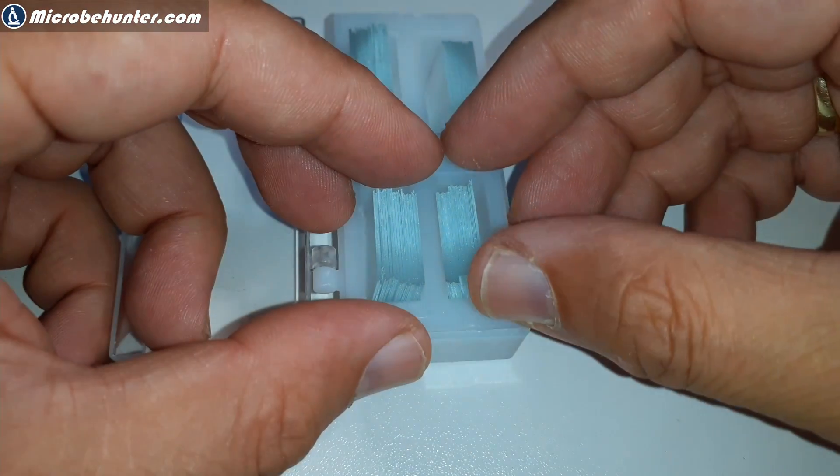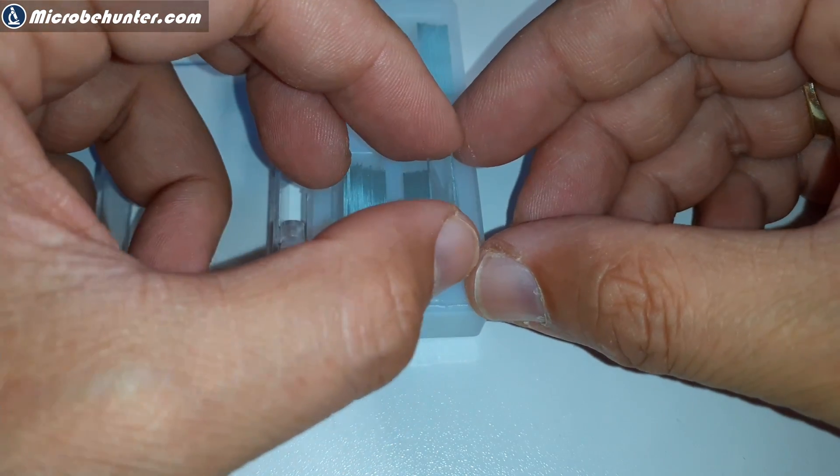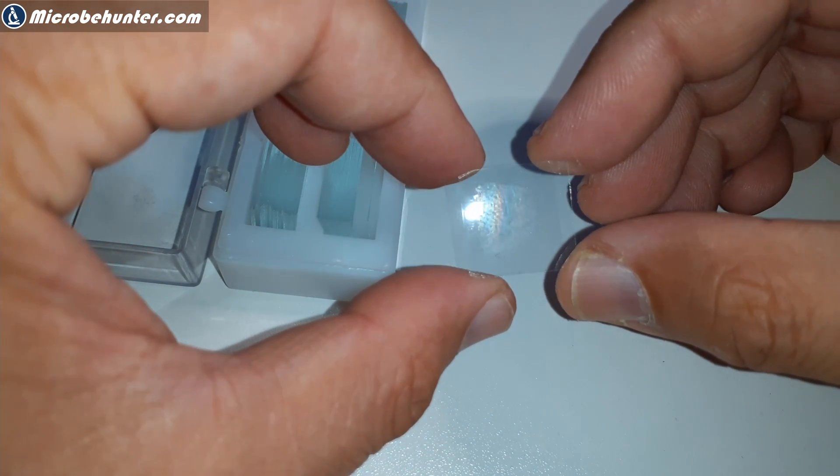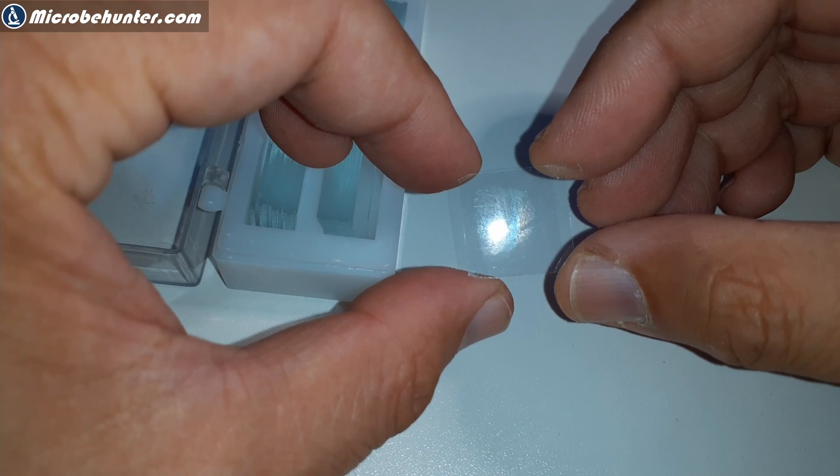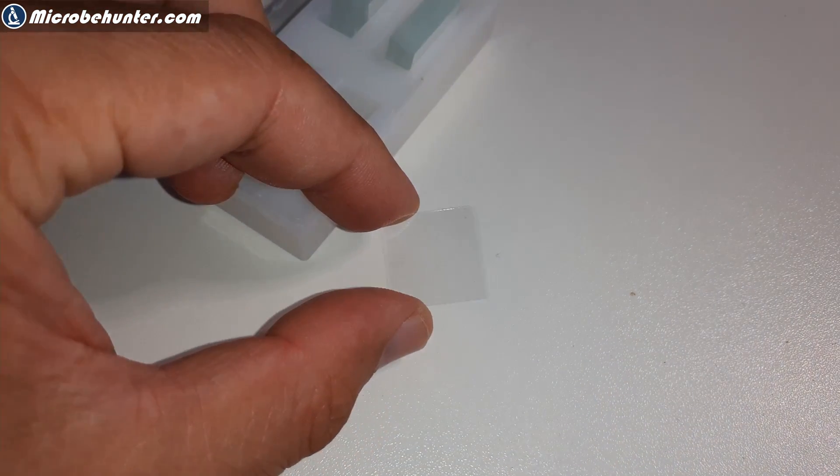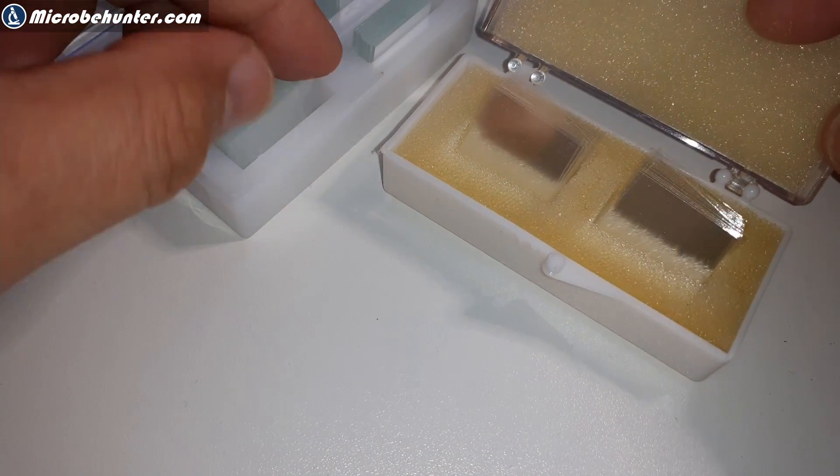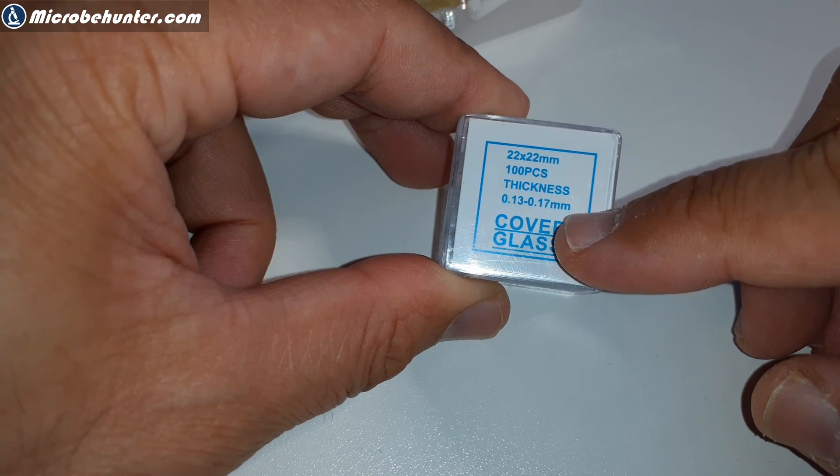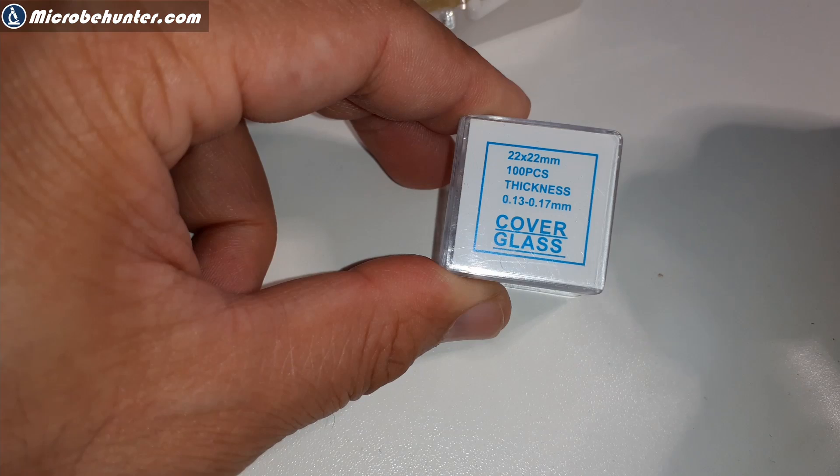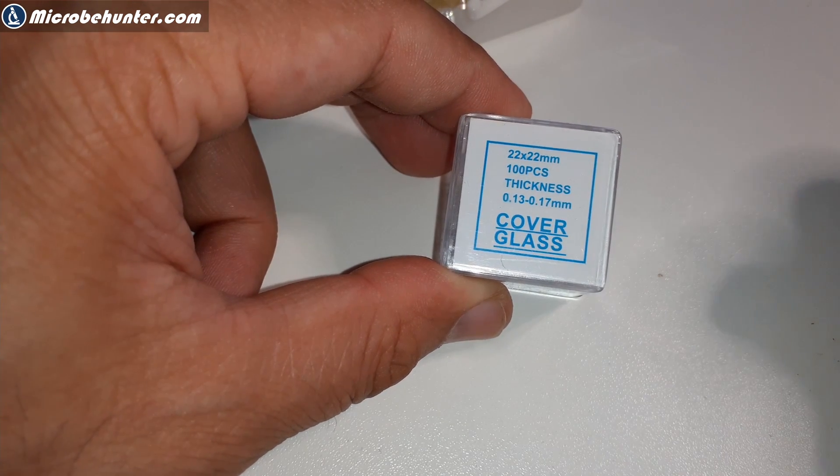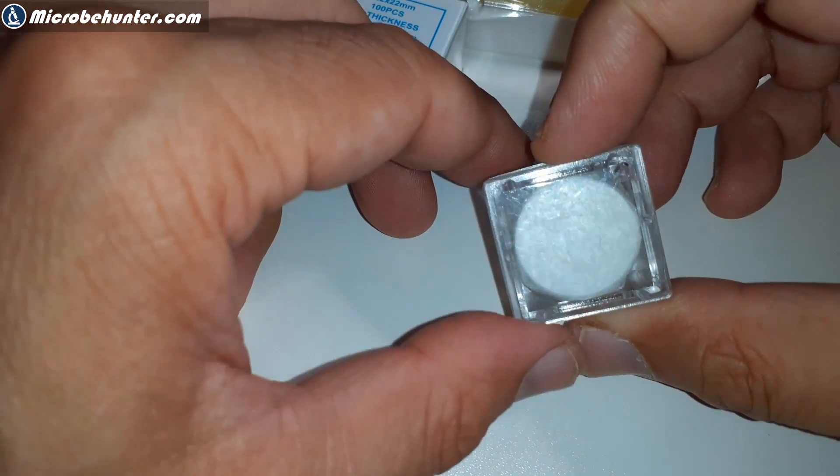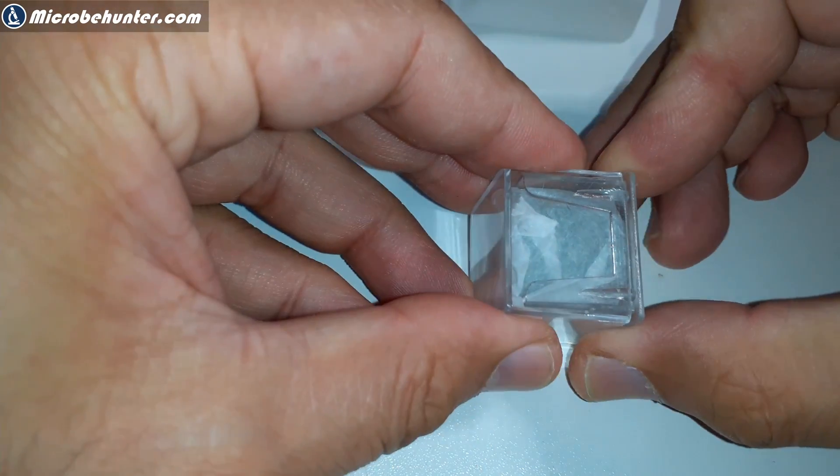Let's talk about those cover glasses here. These are 18-millimeter cover glasses, and they're about 0.17 millimeters thick. They're also not entirely clean, but not a big problem because I will dry wipe them. Looking at the reflection of the lamp is always a very good way of determining if the slides are clean or not. These are slightly larger ones, 22 millimeters in size. This one over here is also 22 millimeters and has a thickness of 0.13 to 0.17 millimeters. The thickness is important because it does influence the resolution a little bit, and most objectives are for cover glass thickness of around 0.17 millimeters.